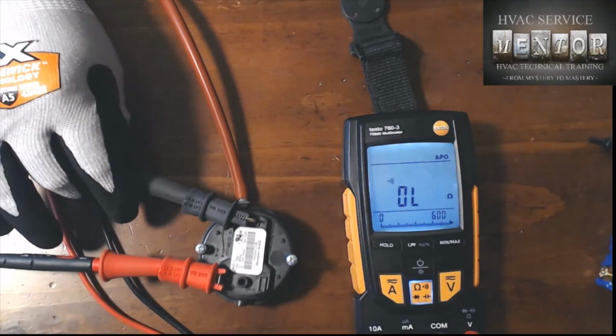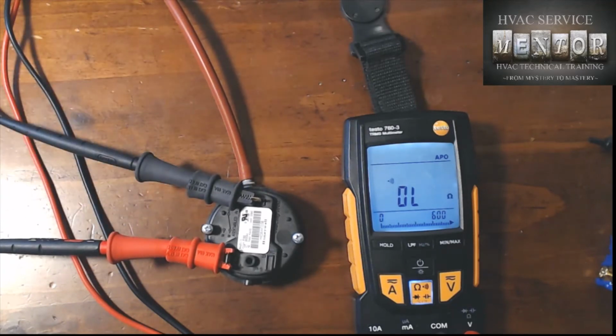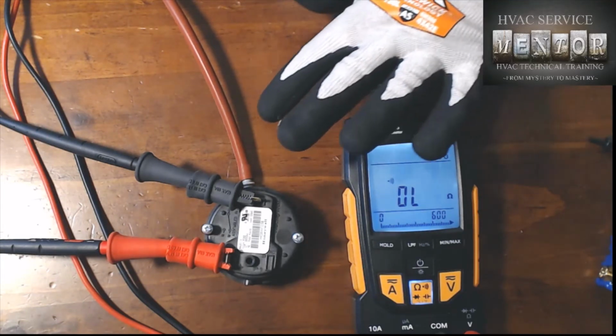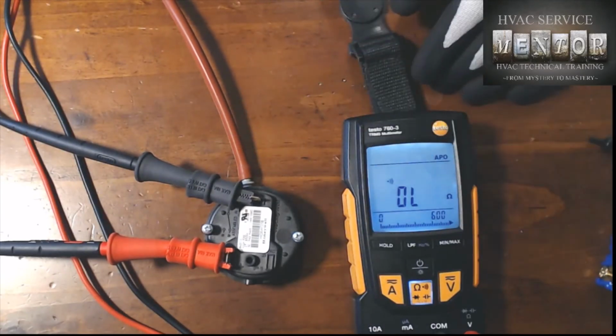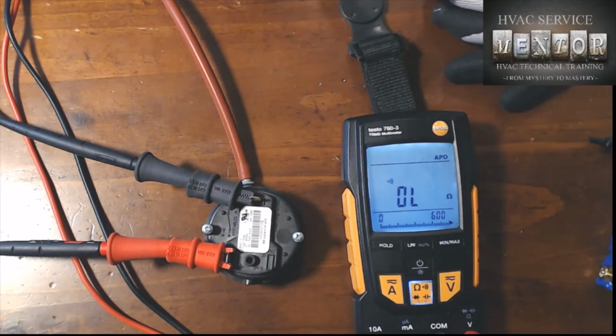But a switch like this pressure switch from a gas furnace doesn't show you whether it's open or closed. Gas furnace pressure switches are supposed to be normally open, and then when a negative pressure is applied to the tube, they're supposed to move to the closed position. We can test that with a continuity tester like this one.